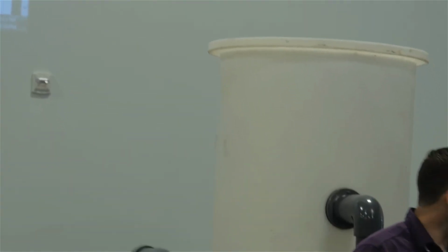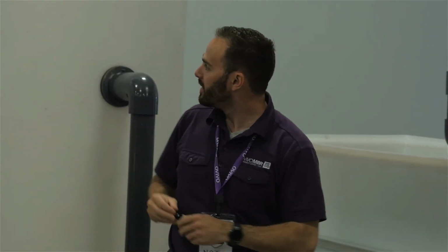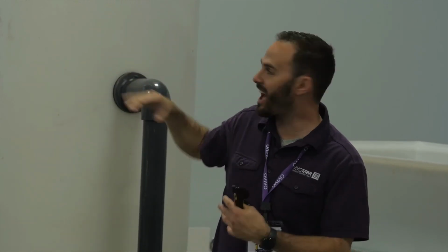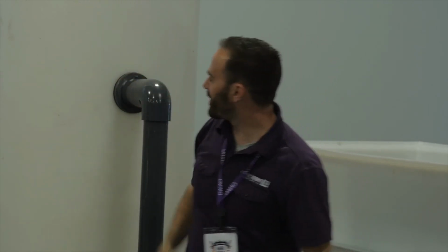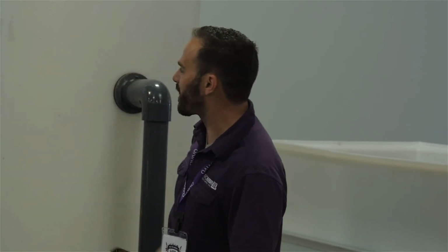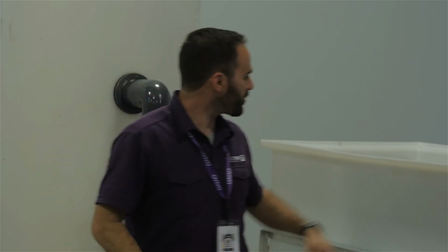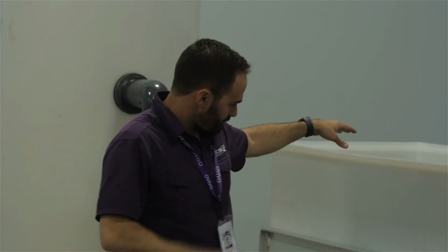So what we want to show you here is that air bubbles going through a turbidimeter will have an effect and raise your turbidity. And that can get really, really high too. That's a pretty small change right there, but once the system's running again with that air coming in, there we go. And another thing to note as well, that pipe was empty right there. It just totally drained out.